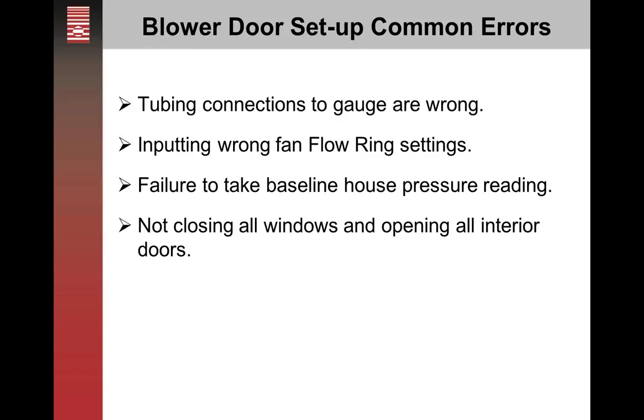Another important part is making sure that you have flow rings. Sometimes people will add the flow ring to the fan itself while it's in the doorway, but then forget to make the adjustment on the gauge to go from open to ring A, and now your number will be a little bit out of sync.